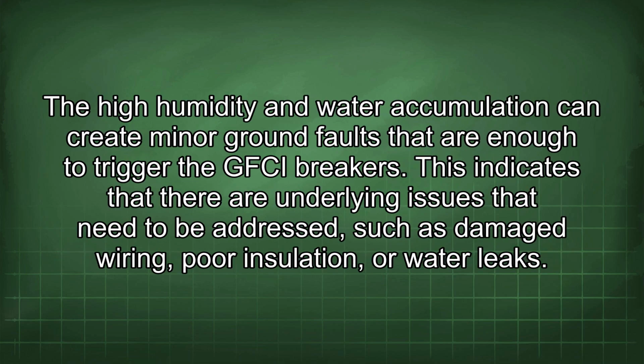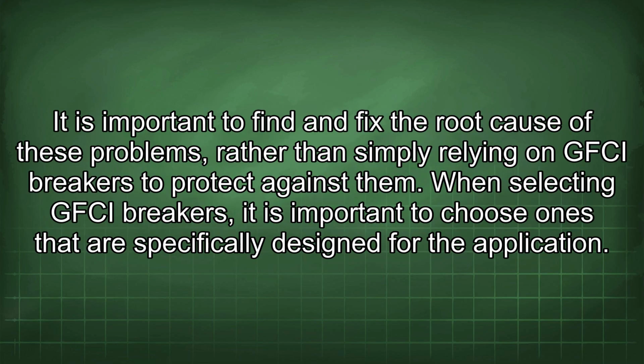The high humidity and water accumulation can create minor ground faults that are enough to trigger the GFCI breakers. This indicates that there are underlying issues that need to be addressed, such as damaged wiring, poor insulation, or water leaks. It is important to find and fix the root cause of these problems rather than simply relying on GFCI breakers to protect against them.